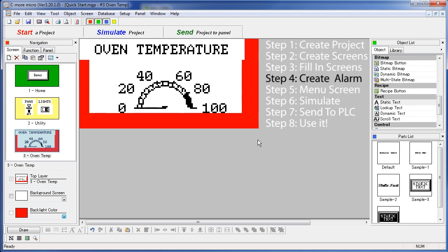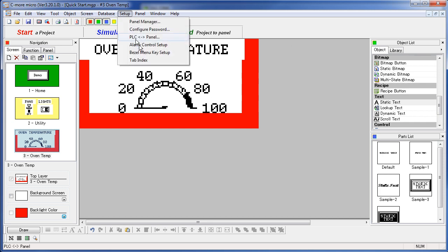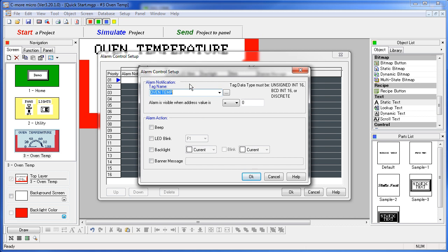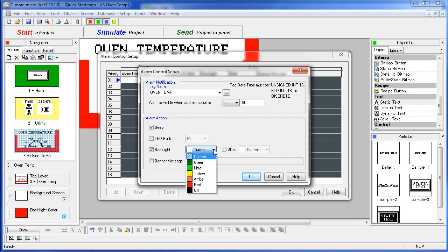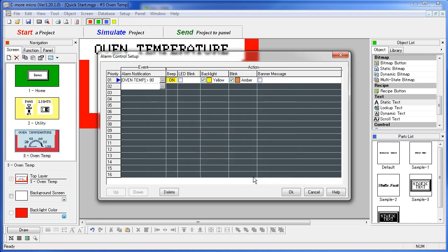Step 4 – we need to create an alarm when the temperature gets over 80 degrees. To do that we go to Setup – Alarm Control Setup. We choose our oven temperature tag. When the oven temperature tag is greater than 80, we want beeps to sound and have the backlight toggle between yellow and amber. So there is our oven temperature tag alarm.